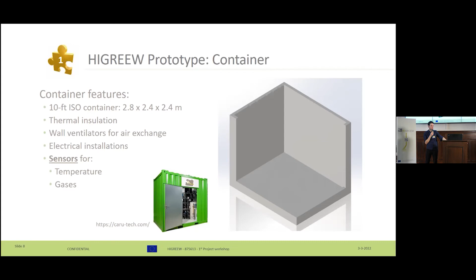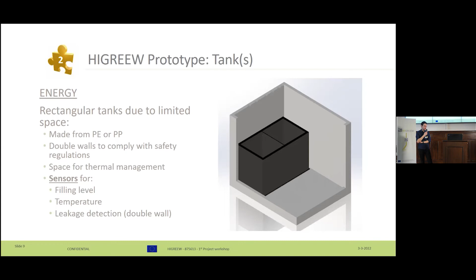So the two main components are, of course, electrolyte and stack. For the energy part, which is the electrolyte, we chose to go with a rectangular container, a rectangular tank. They can be made relatively cheap from polyethylene or polypropylene. They will have double walls to comply with the safety regulations, and they will need to have enough space for thermal management, which I go into in a bit more detail later. And of course, we also need some sensors for filling level, temperature, and leakage detection, which will be inside the double wall.